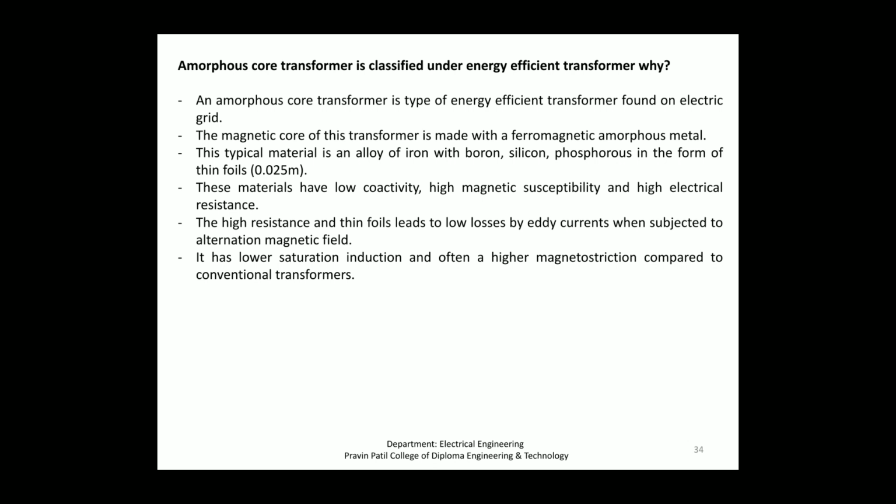Amorphous transformers use a metallic glass alloy for the core. The reduction in energy loss over a conventional transformer is about 70%. They have increased efficiency even at low loads, that is, 98.5% efficiency at 35% load.